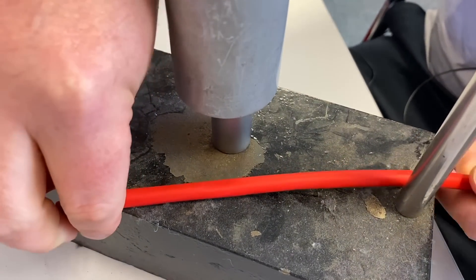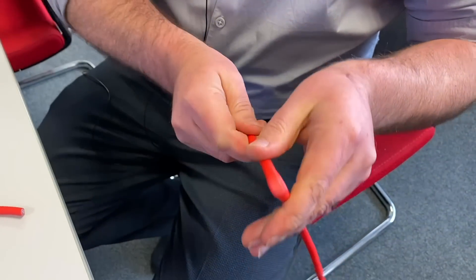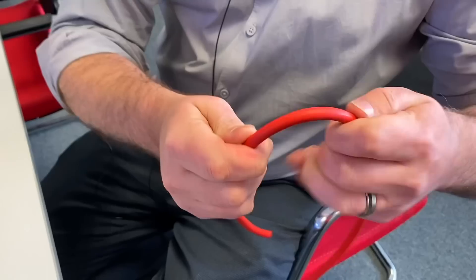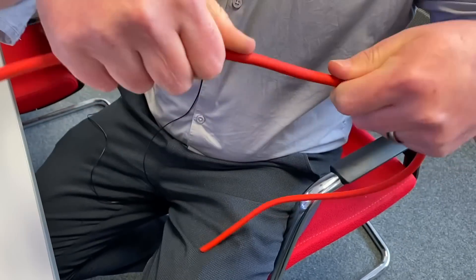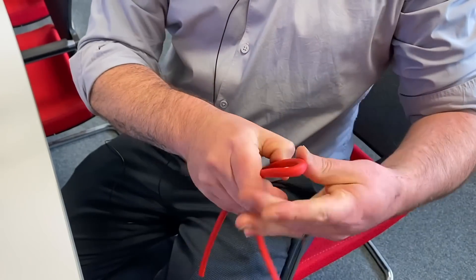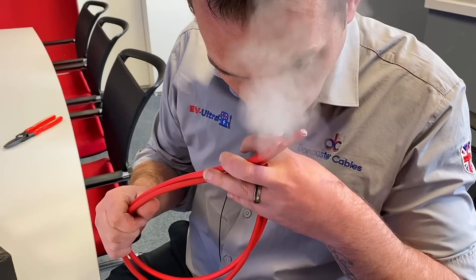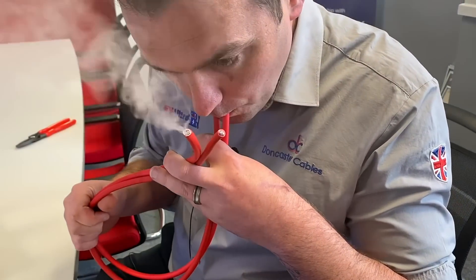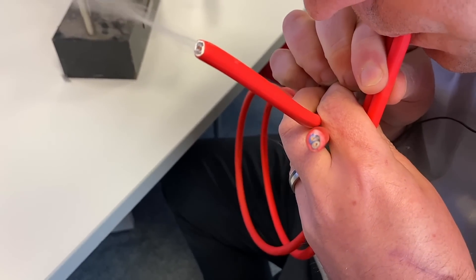The cable is also more resistant to kinks. As you're pulling it through tray work, if it were to kink over, it would go back to its original shape and again protect the cores. Another key feature is smoke transmission — a competitor's cable could act like a conduit, allowing smoke to be drawn into another room. But because ours is filled, there's no smoke transmission in the cable.